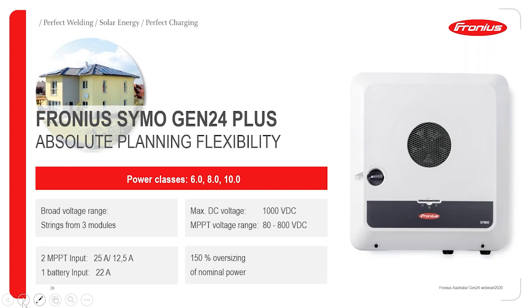This is where it gets really interesting, with the award that we got for the efficiency. Just to give you an example, as I was mentioning a bit at the start, if you have a 10 kilowatt Symo Hybrid, you will be able to put 15 kilowatt on this inverter. The amount of power that this inverter can convert from DC to AC is 10 kilowatt. The amount of power that it can harvest is 15 kilowatt. So what do I mean by that? Let's say your load is asking for 10 kilowatt.